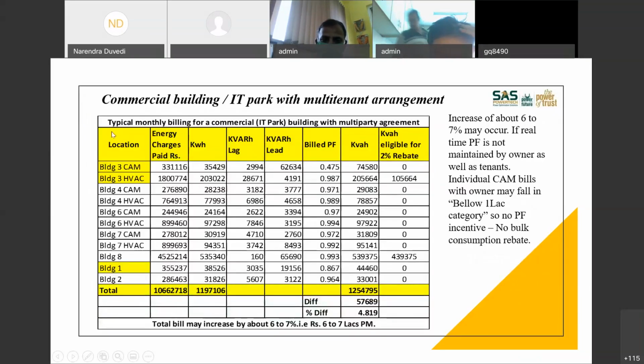Let's take another example of a commercial building or IT park. Typically, all of us know that for commercial buildings and IT parks these days we have multi-party tariff or multi-tenant tariff systems imposed by MSEDCL and all these DISCOMs. Because of that, each individual consumer in your building will have his own meter, for which he pays the utility directly, and only the balance all-area consumption comes under those who are maintaining the buildings. Because of that, it is quite likely that the consumption can go below 1 lakh, 10 lakh kVAh, and they will not get any discount.